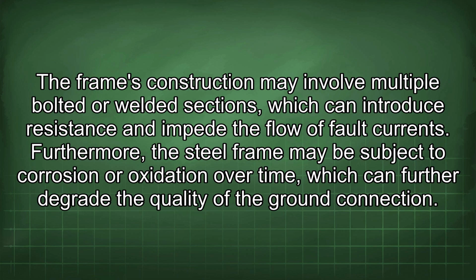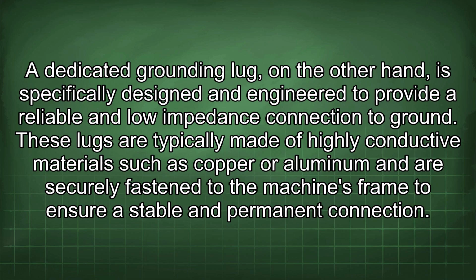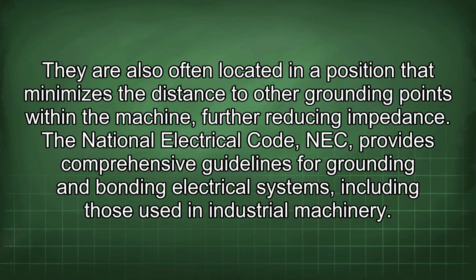the ground connection. A dedicated grounding lug, on the other hand, is specifically designed and engineered to provide a reliable and low impedance connection to ground. These lugs are typically made of highly conductive materials such as copper or aluminum and are securely fastened to the machine's frame to ensure a stable and permanent connection.